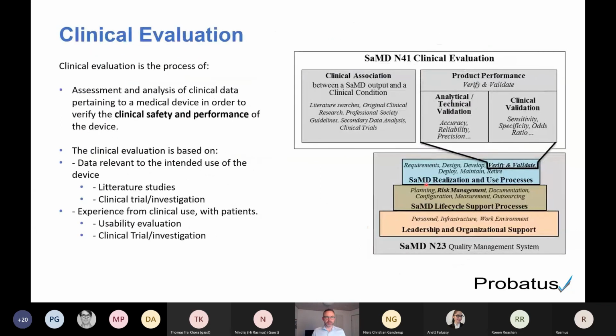The evaluation is established by assessing and analyzing clinical data pertaining to the device in order to verify clinical safety and performance. It can be done based on literature or on data, including usability, and the risk analysis is important as part of the input to this. And it can be, if we are using equivalent data, from a device that we can actually make use of. It could be one of our own products, but it could also be a competitor if they are willing to share that data with us.